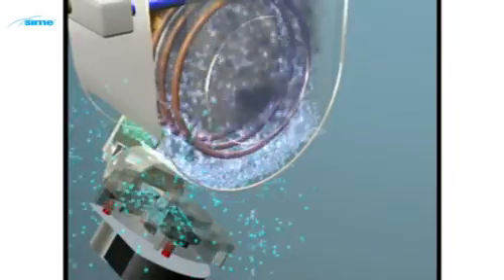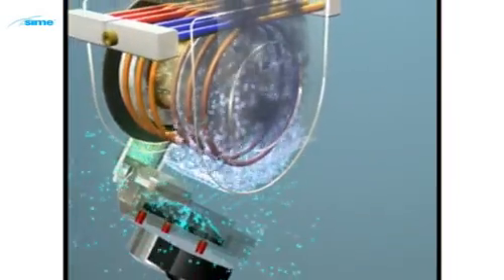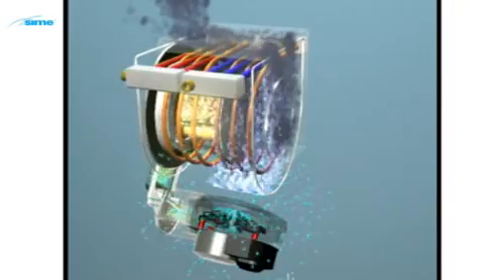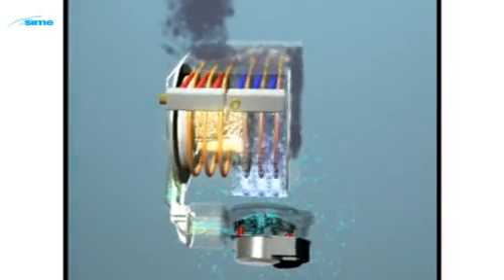Unlike conventional boilers, which have a fixed speed fan, the gas valve is modulated to vary the output. In this arrangement, the gas valve is fixed, and the fan speed is modulated.